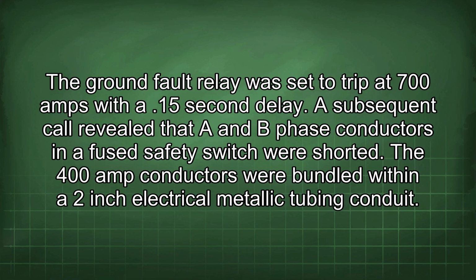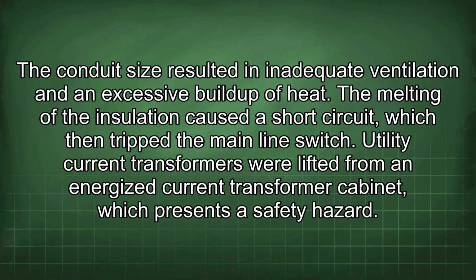A subsequent call revealed that A and B phase conductors in a fused safety switch were shorted. 400 amp conductors were bundled within a 2-inch electrical metallic tubing conduit. The conduit size resulted in inadequate ventilation and an excessive buildup of heat. The melting of the insulation caused a short circuit, which then tripped the main line switch.